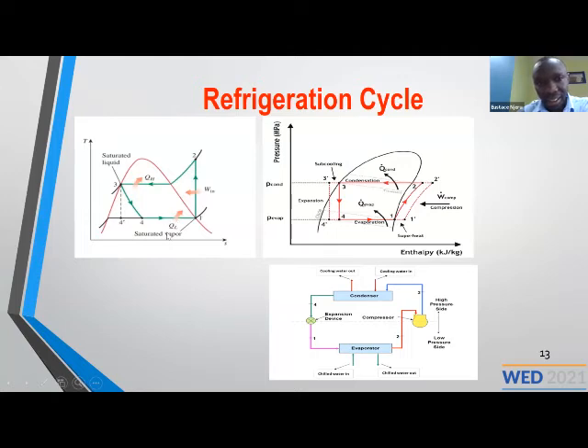In most cases, at the evaporator and the condenser, here we have heat exchangers. So in the refrigeration cycle, you don't have any energy consumption here. What you have is the heat exchange between the media being cooled and the refrigerant, and the cooling media. In this case, if it's a water cooled chiller, you have water. If it's an air cooled chiller, you have air. So one of the areas you have to concentrate on mainly, and the reason why you have to understand the refrigeration cycle, is to know the power. The length of this line represents the power, the input power to the chiller.